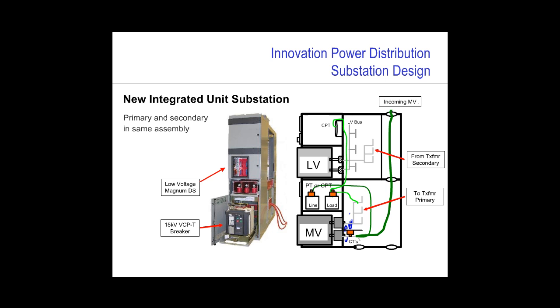So following the power flow in the section view on the right, you can see my incoming cable would come in from the top in the darker green, move into the medium voltage breaker, and back through the breaker into the transformer compartment. And I show PTs and CPTs in this section as well. And then the secondary of the transformer is on the same side and comes back into this enclosure, feeding into a low voltage main power circuit breaker, which then feeds low voltage bus and feeder breakers.